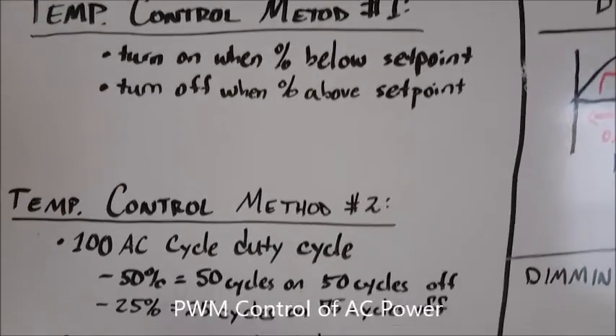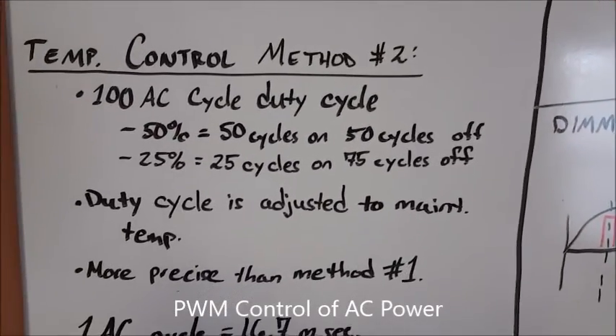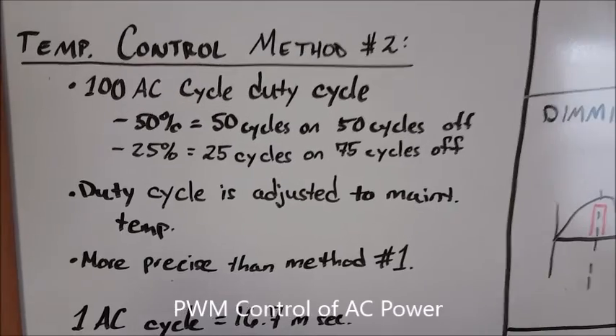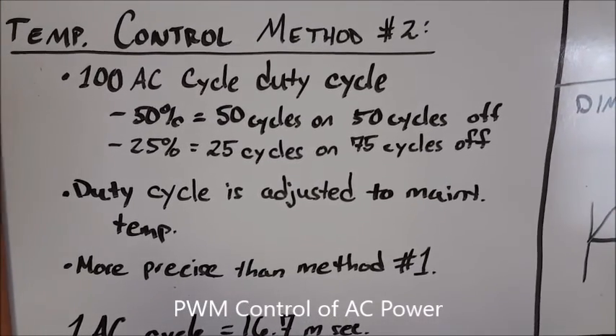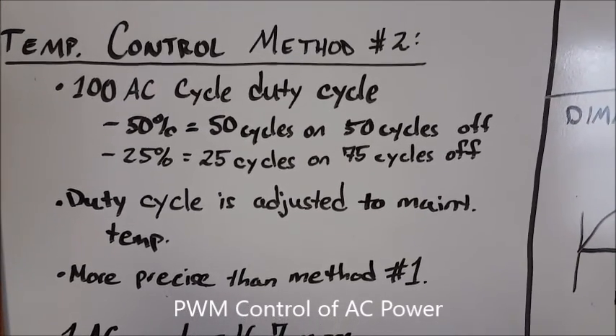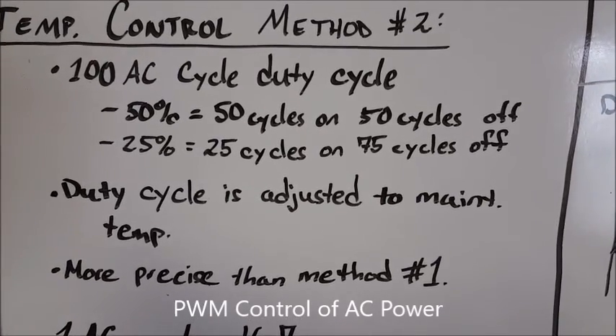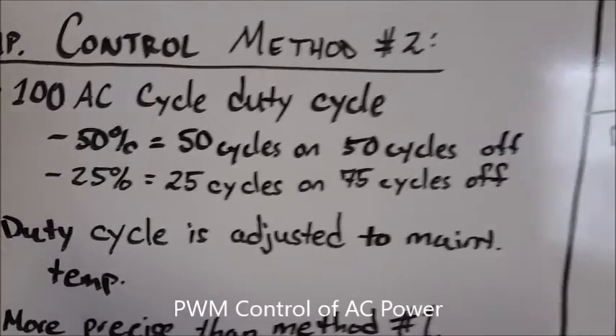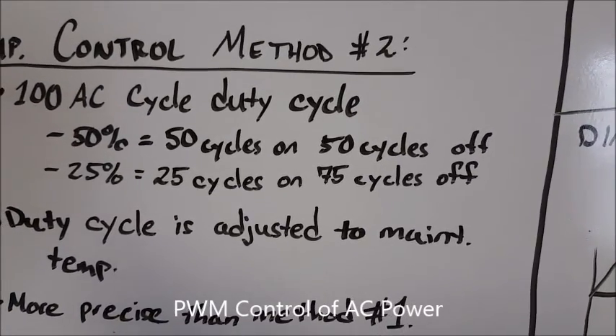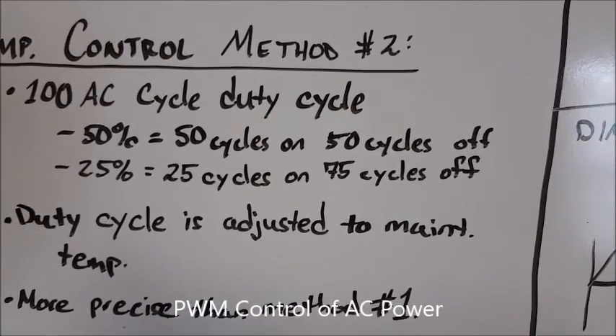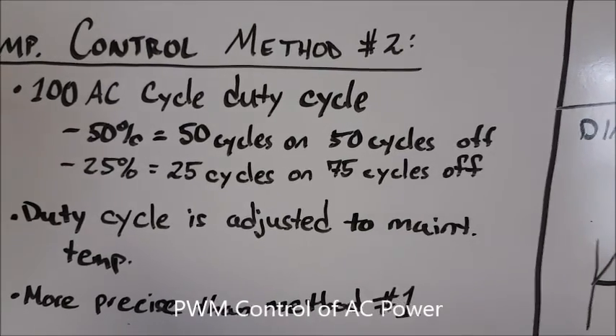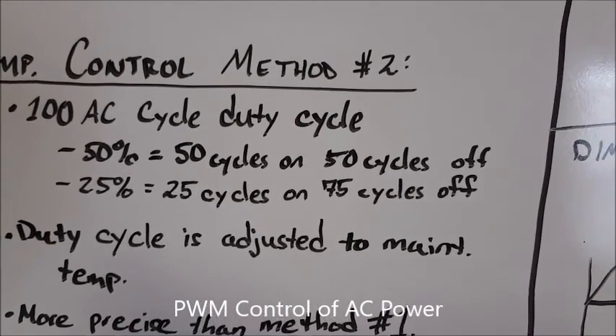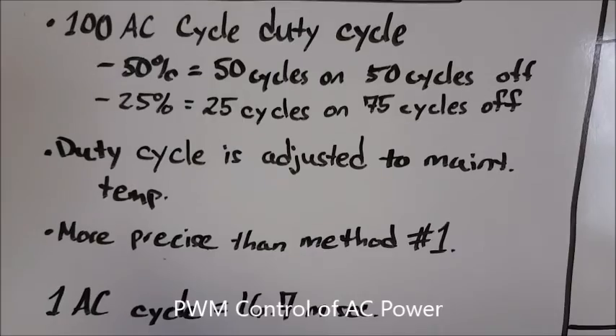A better method of temperature control is method number two, using a 100 AC duty cycle. 100 cycles of AC equals one control cycle, so 50% on would equal 50 AC cycles on and 50 off. A 25% duty cycle equals 25 cycles on and 75 off.